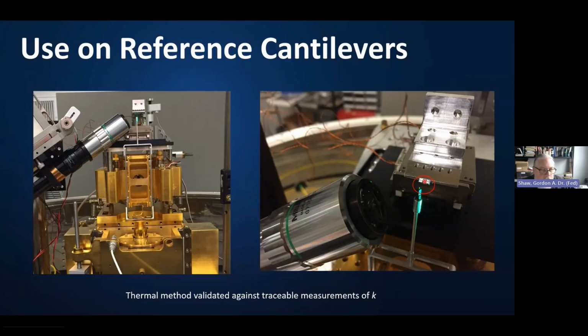You can see here, this is a large-scale picture. You'll recognize this is the electrostatic force balance I showed earlier. And we have a sharp probe tip here. And these small objects here are the reference cantilever arrays. What we can do is we can bring this sharp probe tip into contact with one of the cantilever springs. We can apply a known force using our electrostatic force balance, and since there is a known displacement from the laser interferometer, remember the spring constant is the force divided by displacement, we have all we need to generate a traceable spring constant.